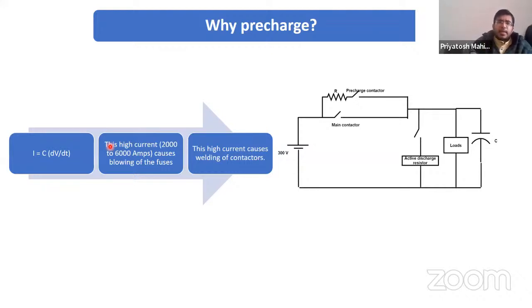Here you can see the battery; we've taken an example of 300 volts, which is very high voltage compared to what we typically see in machine drives. You can see several contactors, including a very important active discharge resistor, and another component, the pre-charge contactor. When the pre-charge contactor is closed, the main contactor will be open; normally open and normally closed, NO/NC, communicate with each other.